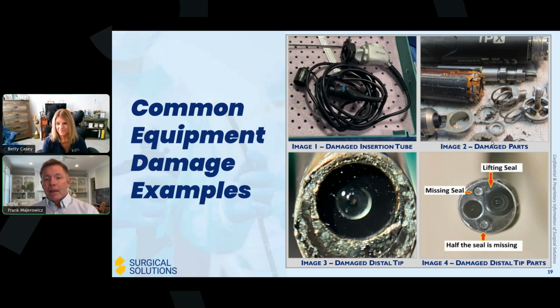But no, if you look at this, so image number 1, that's a camera head. Okay, so it's a Stryker camera head. You can't really see any specific damage to this picture, but I'm sure there's some smiles out there. And the comment I'm going to make about this is the number 1 issue with camera heads is damage to the cable. Okay, that cable, as you all know, if you've handled a camera before, is at least 6 foot long, maybe 6 to 8 foot long, and it connects the camera head back to the processor on the cart to give you an image.